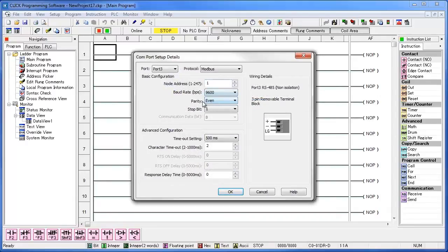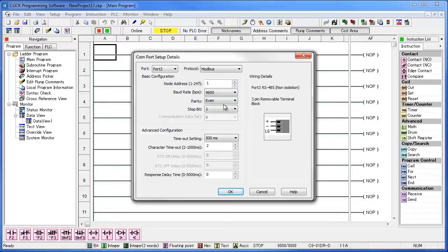Make sure the node address is set to 1. Setting the node address to 1 is telling the CLICK that this port is the master and not the slave. You want to make sure that the baud rate, the parity, and the stop bit match what you saw on the SOLO. You can change the baud rate, parity, and stop bit, but just make sure that they match up on the CLICK and the SOLO.